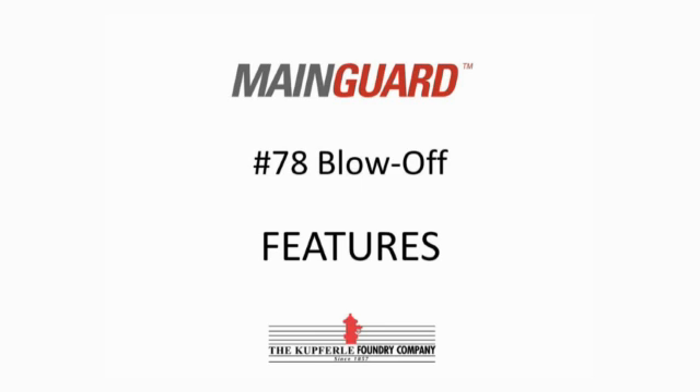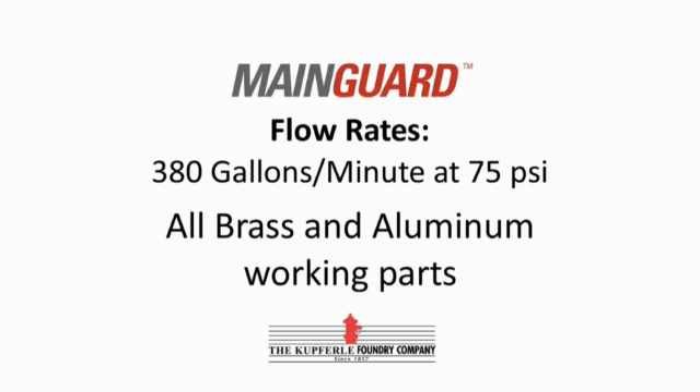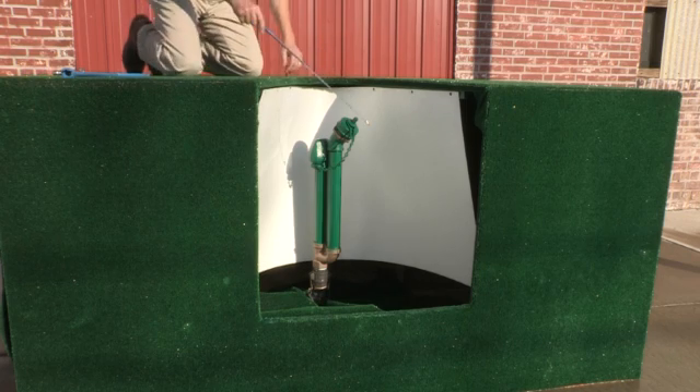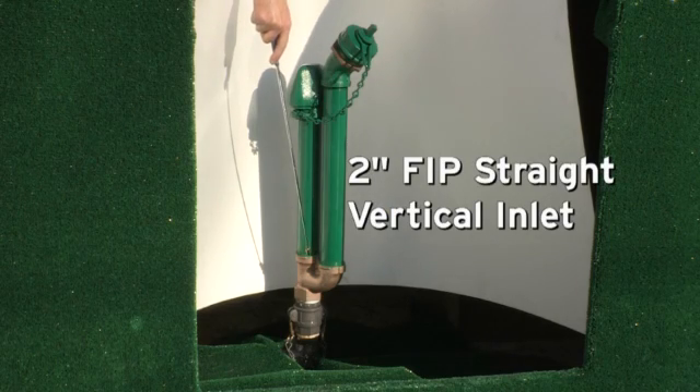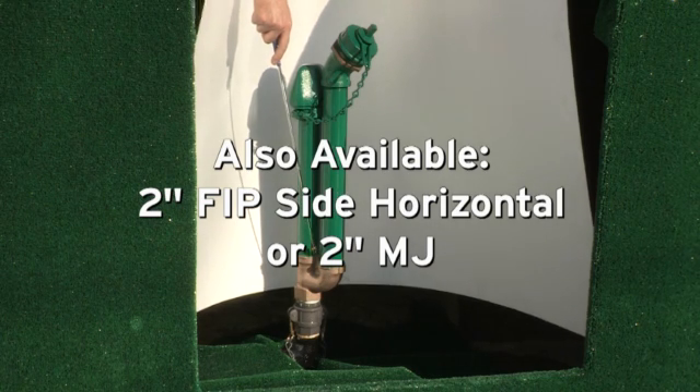This is the MainGuard 78, a 2-inch below-grade blow-off self-draining non-freezing hydrant. It has flow rates of 380 gallons per minute at 75 PSI. It features all brass and aluminum working parts. The MainGuard 78 features a 2-inch FIP straight vertical inlet. A 2-inch FIP side horizontal or 2-inch MJ is also available.